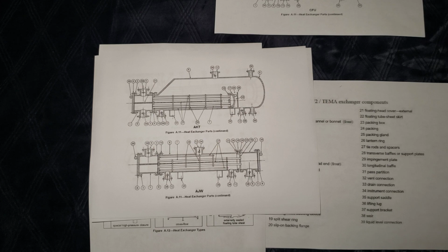When we have original construction drawings available, we should compare them to the previous reports available. Hopefully they match, and if they don't, that we reconcile our report with the original construction drawing and translate the previous. That way they all compare to the same.